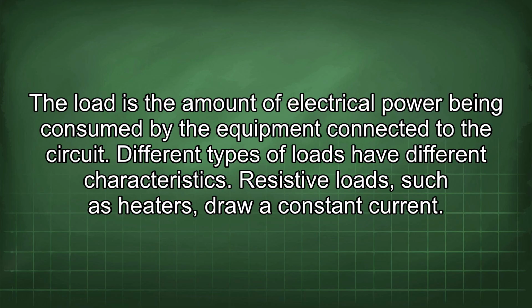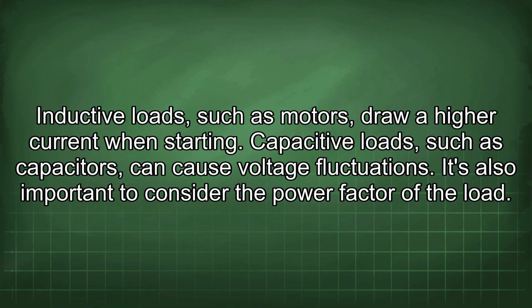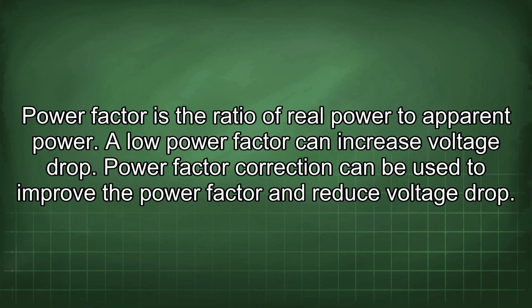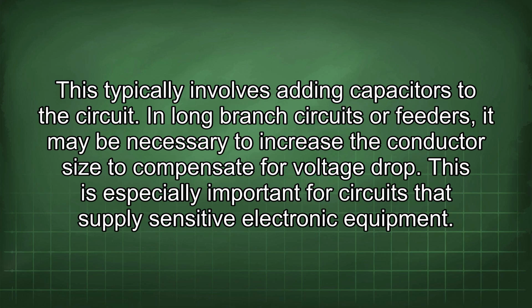The load is the amount of electrical power being consumed by the equipment connected to the circuit. Different types of loads have different characteristics. Resistive loads, such as heaters, draw a constant current. Inductive loads, such as motors, draw a higher current when starting. Capacitive loads, such as capacitors, can cause voltage fluctuations. It's also important to consider the power factor of the load. Power factor is the ratio of real power to apparent power. A low power factor can increase voltage drop. Power factor correction can be used to improve the power factor and reduce voltage drop. This typically involves adding capacitors to the circuit.